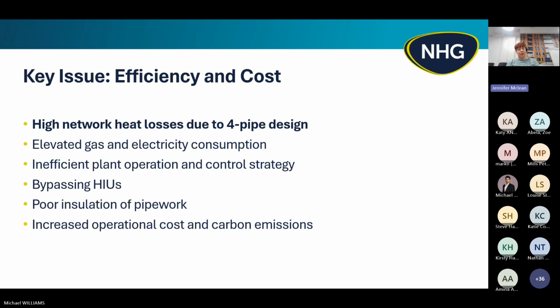When Fairheat carried out the study, they identified key issues affecting efficiency and cost, including significant heat losses due to the pipework design, elevated gas and electricity consumption, and inefficient plant operation and controls. The heating units within dwellings were not performing well, some units were bypassing, and insulation was not of a good standard, with areas missing and generally not compliant with current building regs in terms of thickness. All of this increased our operational costs significantly and resulted in quite high carbon emissions from the site.